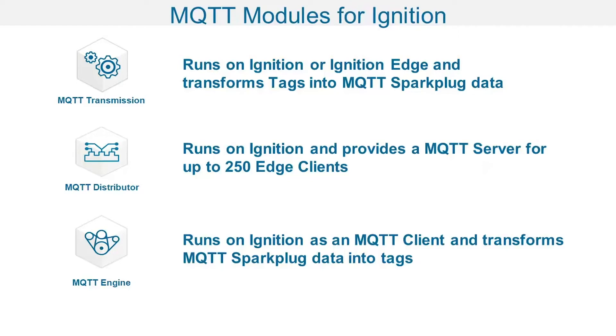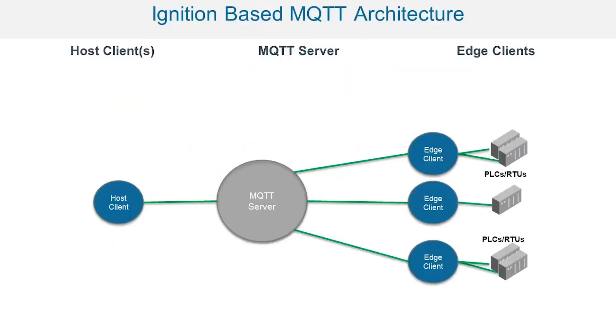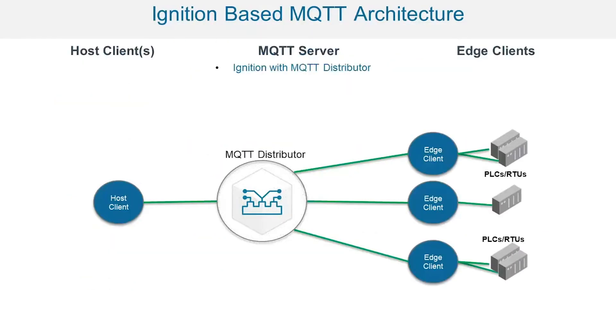Let's look at using MQTT modules for Ignition and a different architecture. MQTT Transmission takes tags in an Ignition tag database and publishes them using MQTT Sparkplug. MQTT Engine, conversely, subscribes to Sparkplug messages and automatically creates Ignition tags. And finally, we have a module called Distributor that provides an MQTT server as an Ignition module. Using those components, we can install MQTT Distributor and have our MQTT server functionality.